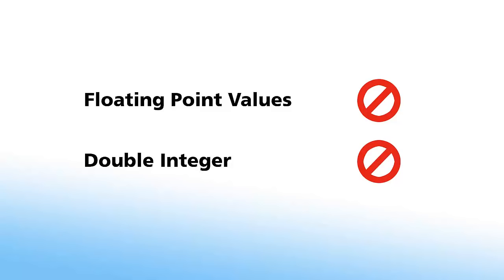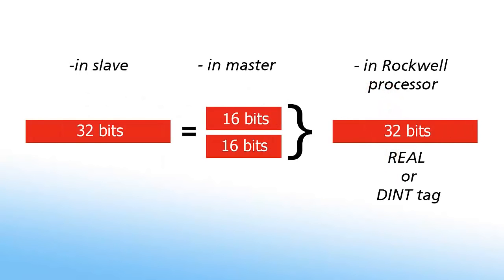This presents a small problem since Modbus does not have a float or dint data type. The solution, obviously enough, is that the 32-bit value is broken into two separate 16-bit registers, and then recombined into a 32-bit real value.